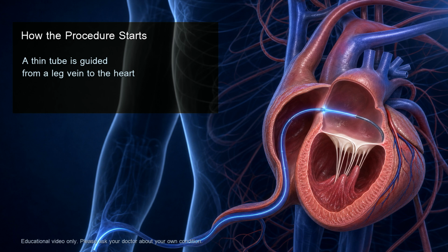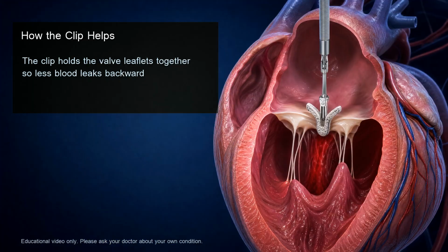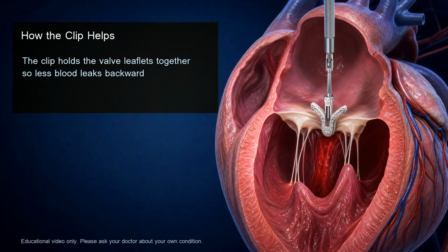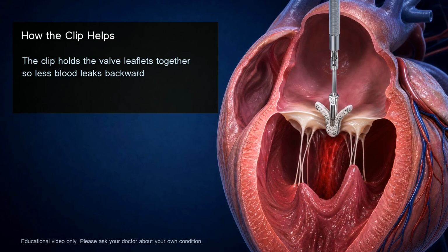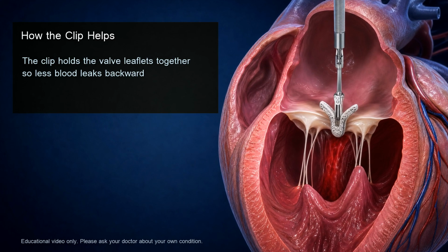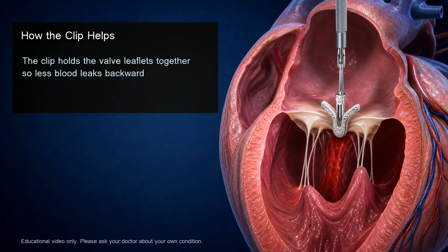Once the catheter is in the right position, the clip is moved above the leaking part of the valve. The clip arms are opened, and the doctor carefully catches the front and back valve leaflets. When the leaflets are held together, the valve can close more effectively. This usually reduces the amount of blood leaking backward. Sometimes one clip is enough. In other cases, more than one clip may be needed. Before releasing the clip, the team checks the result very carefully. They look at how much leak remains, whether the valve is opening well enough for blood to pass through, and whether the clip is stable. If the result is good, the clip is released and stays attached to the valve. The catheter is then removed.